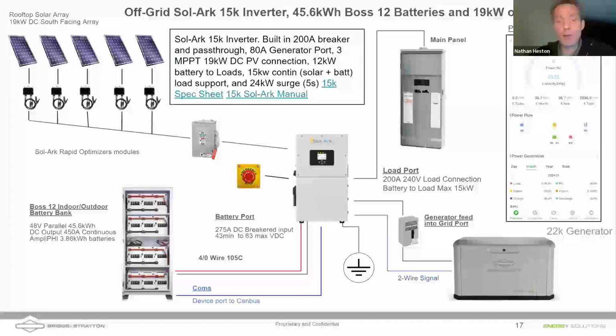We've got a bigger battery bank here than the 20 kilowatt hour battery bank I showed on the last slide, because typically off-grid customers need a little bit larger battery bank to get them through those longer outages with maybe solar not producing as much on those cloudy days, etc. But what we're looking at here is just a single panel, and this would be the same whether this is a Sol-Ark 15K or even just a smaller Briggs 6K inverter. But the advantage you have here is you can bring a 22K generator in through that 200 amp grid connection. You can bring a 26K generator in.